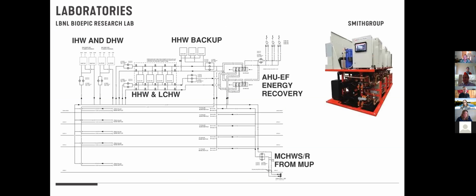I won't dive too far into the piping schematic for this project, but the same water source heat pumps with heat recovery can provide all sorts of grades of energy: heating hot water, low temperature chilled water, medium temperature chilled water, medium temperature heating water, high temperature heating water - we're achieving all of those with heat pumps on site. We're also using heat pumps on this project to provide both industrial hot water and domestic hot water, meaning the potable water at a faucet as well as industrial hot water serving experimental equipment. This project is also using heat recovery off of the exhaust fans.